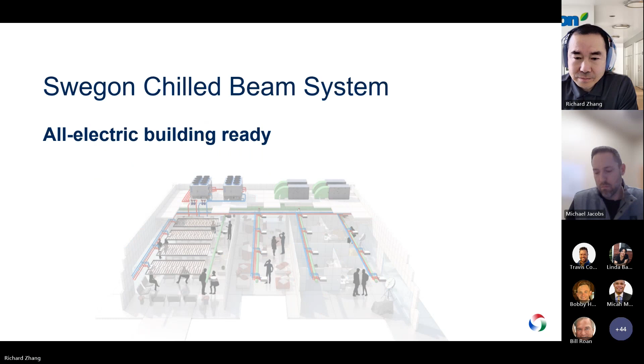So just wanted to go quickly over chilled beams. A chilled beam is a very simple terminal unit. You just imagine there's a coil behind the diffuser. But when you design this, make sure you bear two concepts in mind to design them properly: the capacity equipment with the induction, and at the same time, it's a diffusion equipment. So you want to distribute the air properly.